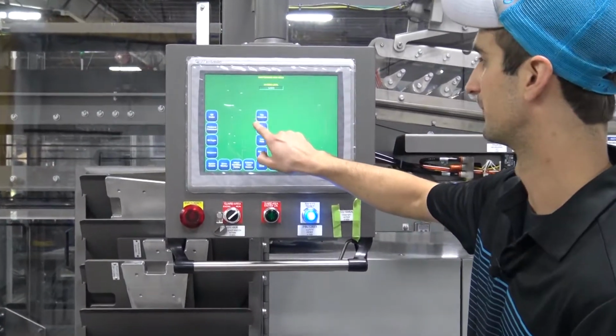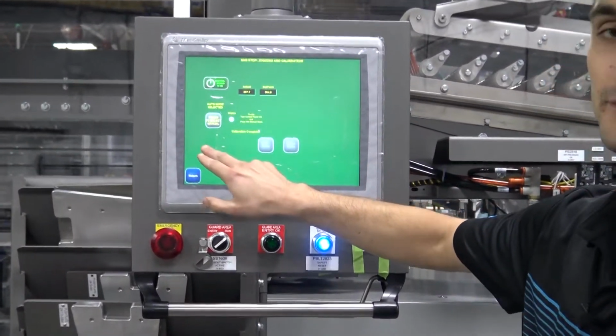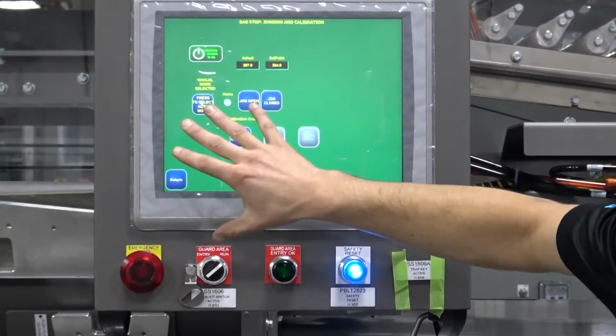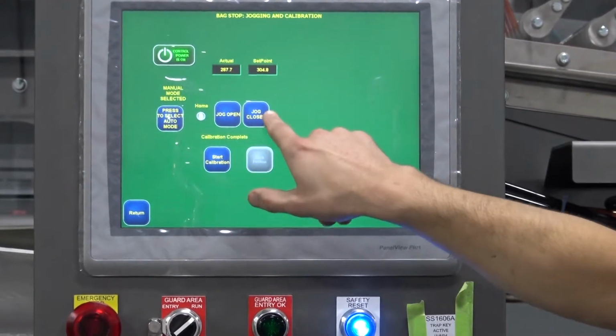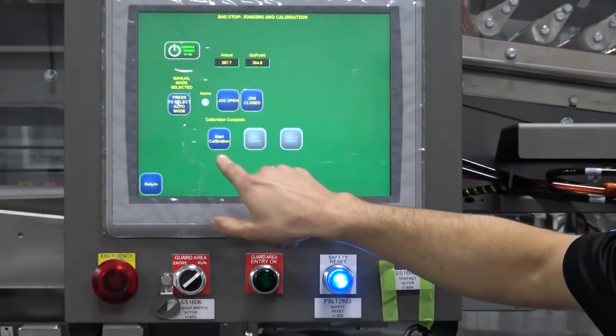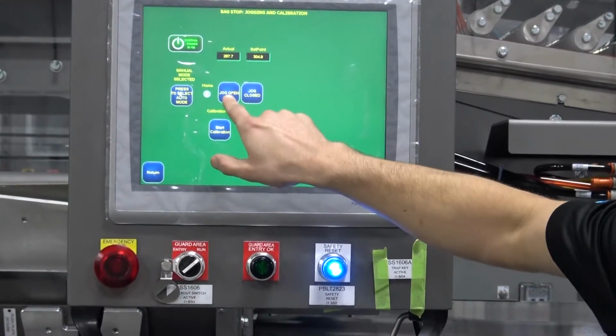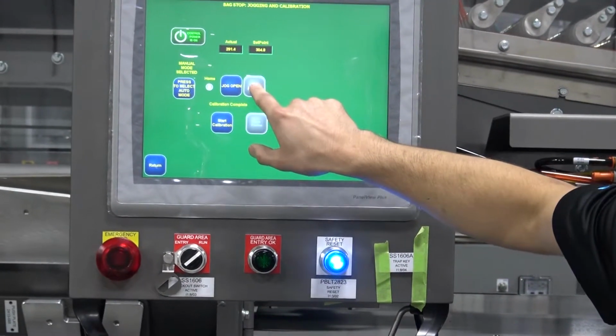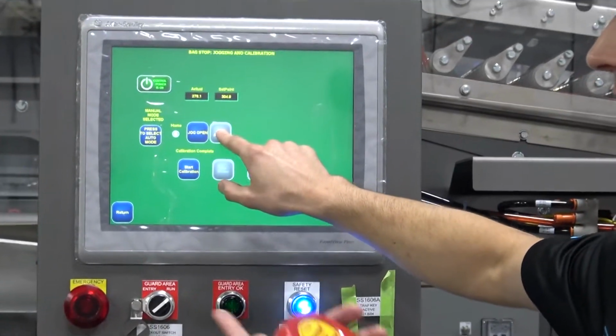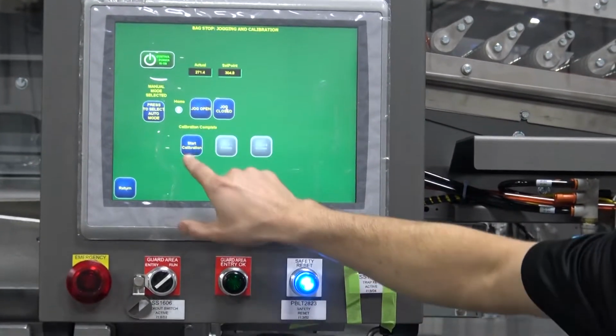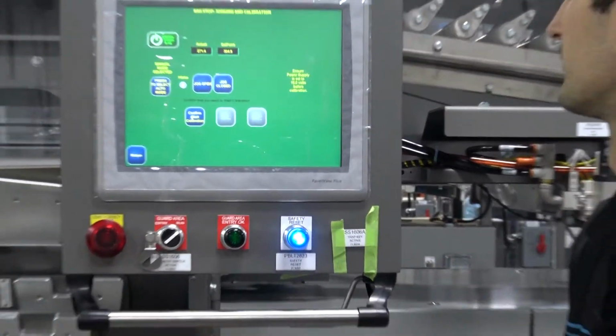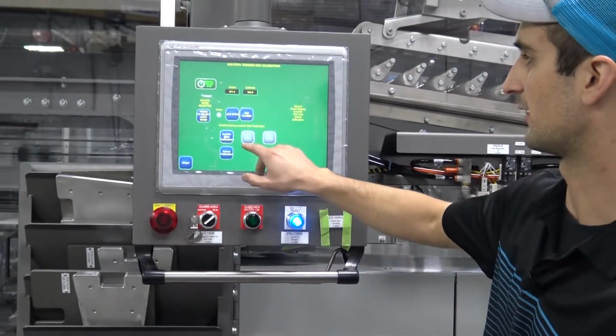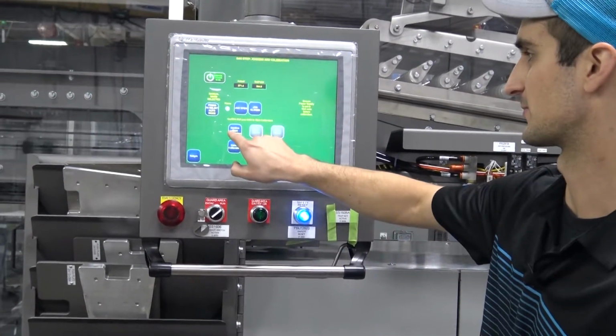and we want to calibrate the bag stop. I'm going to go into manual mode. In manual mode, you get your jog open and jog close push buttons, but I want to start calibration. With these buttons, I can jog it and test it and make sure the actuator is working in the first place, and I see that it is. So I do want to start calibration, and then confirm you want to start calibration. It's a double check that you want to start the procedure.